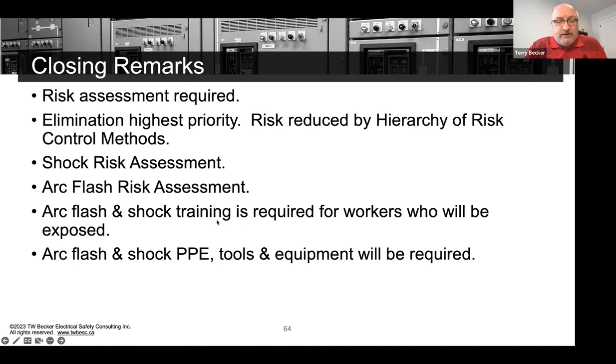Training is required, as I said, and in my opinion the regulator would expect that arc flash and shock training has been provided, and you need to manage that, really at a three-year frequency, which cycles with the three-year cycle of 70E and Z462, and the arc flash and shock PPE. I just highlighted it briefly in this webinar today, but there's a lot more detail that you need to get involved with respect to your specification, your procurement, your inventory management, the dielectric retesting of appropriate shock PPE, and then getting the worker to make sure they do their pre-use inspections and checks right before they use it, and then inventory management and laundering. I didn't mention that, laundering. I'm finding in the last little while that I ask, well, how are you laundering this arc flash PPE?